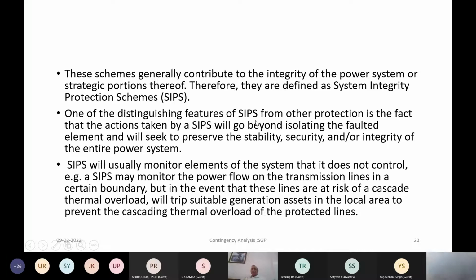One of the distinguishing features of this system integrity protection scheme from other protection schemes is the fact that actions taken by SIPS will go beyond isolating the faulted element and will seek to preserve the stability, security, and integrity of the entire power system. So these are all termed in terms of technology as wide area protection. You must have heard the terminology in PMU. These are called wide area protection because the action is not just confined to one area, but it will encompass multiple areas or even the entire power system as far as the remedial actions are concerned.